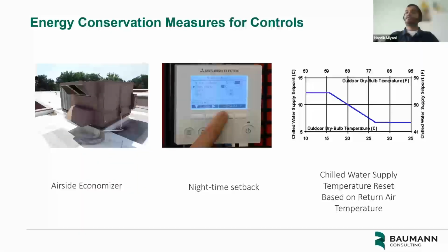And another one is the chilled water supply temperature reset. Depending upon the return air temperature, the building automation system will change the chilled water supply temperature to the cooling coils, which will help to save energy as part of the sequence.